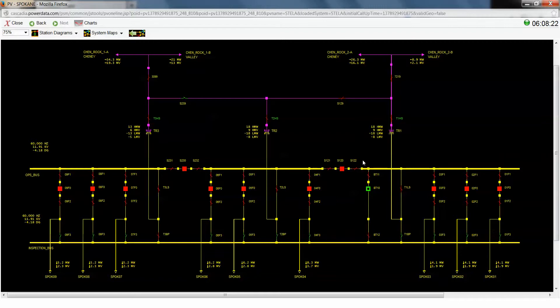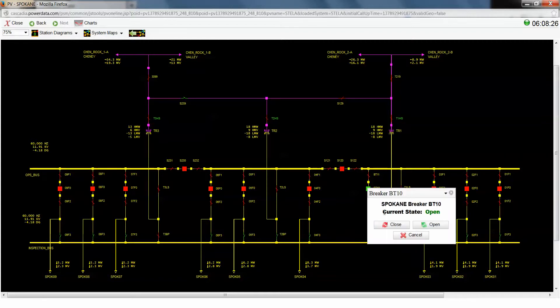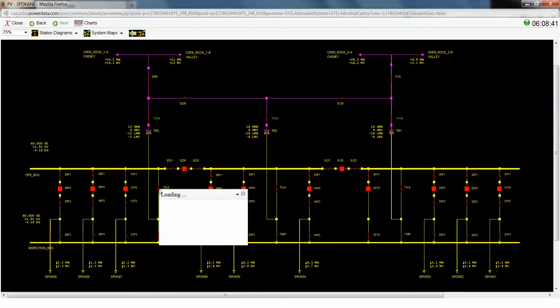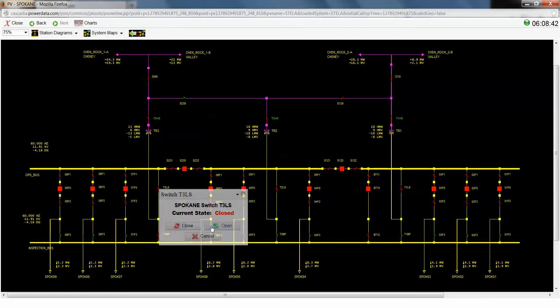Alright, now the very last thing that we have to do before we can open this low side switch is we need to actually make our parallel, which we're going to do across this bus tie breaker right here. Alright, now you'll see that we've created this parallel path, which will allow us to safely operate the low side switch of our transformer three, which we're going to do right now.